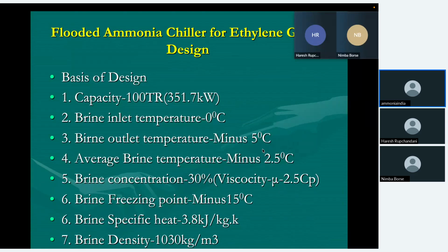Basis of design: 100 TR. Here we don't have to take compressor power consumption into account. We can design the chiller for the exact capacity, whatever the customer requires. Brine inlet temperature is 0 degrees centigrade, brine outlet temperature is minus 5 degrees centigrade. So the average brine temperature is minus 2.5 degrees centigrade.